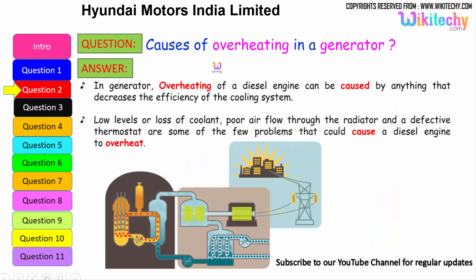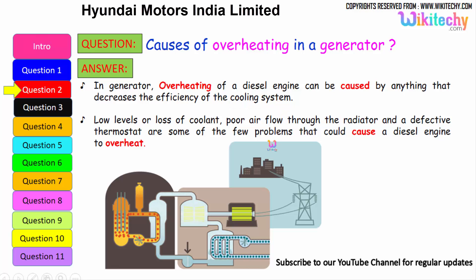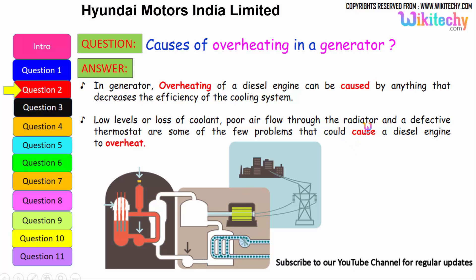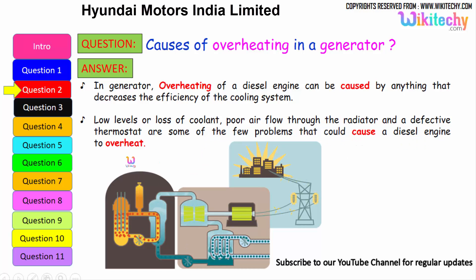Let us move on to the next question: causes of overheating in a generator. In a generator, overheating of a diesel engine can be caused by anything that decreases the efficiency of the cooling system. It can be due to loss of coolant or low levels of coolant, poor airflow through the radiators, and a defective thermostat — some of the few problems that could cause a diesel engine or generator to overheat.